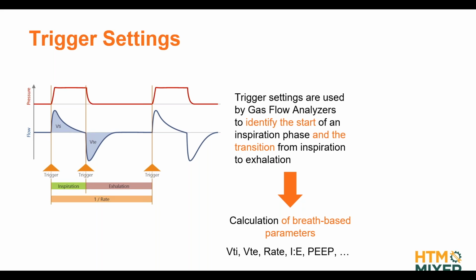You can integrate the flow over that inspiration time and say, okay, that's our inspiration tidal volume, right? Same for exhalation. So in order to measure all these breath-based parameters, your analyzer needs to be able to trigger. If it's not triggering, then you typically see just dashes on your screen, or some ventilators display something called "no trig" or something like that. Also, most gas flow analyzers have some kind of indicator on the screen that tells you when it's triggering. For example, with ours, it's a T that flashes up on the display each time it's detecting a trigger. So if you don't see that happening, if you don't have a measurement of these breath-based parameters, then that means your gas flow analyzer is not triggering. So again, we need triggering to be able to measure all these parameters.